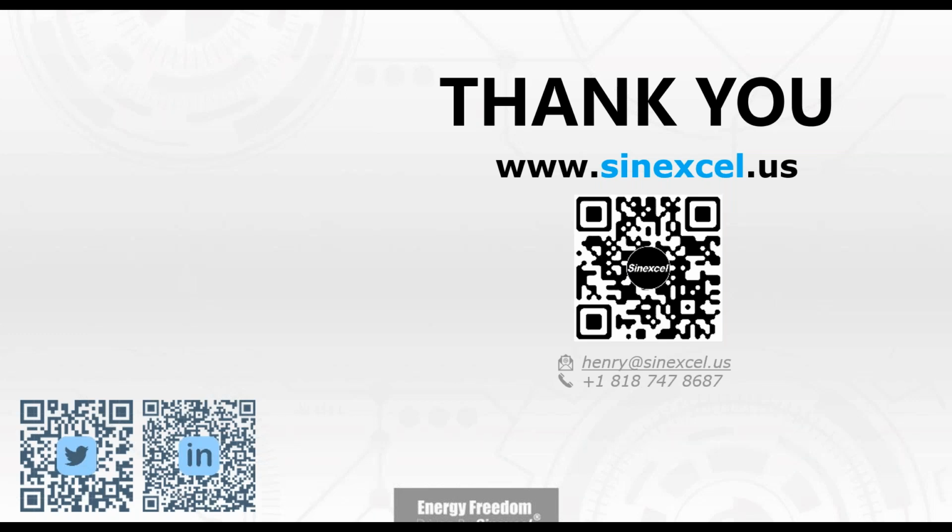For the PV side, I believe it's also related with whether it is grid-tied or off grid. Marty made a very good point: if there is a zero export, then a higher or larger PV cannot generate much economic value. For the off grid application in a DC coupled system, there are very limited restrictions, because in a DC coupled system it's more related with the PCS power. But for the AC coupled system, it is recommended that PV power not exceed the PCS or storage power. Otherwise, the whole microgrid might face stability challenges. But as I mentioned, it varies, with too many different applications in the C&I sector.